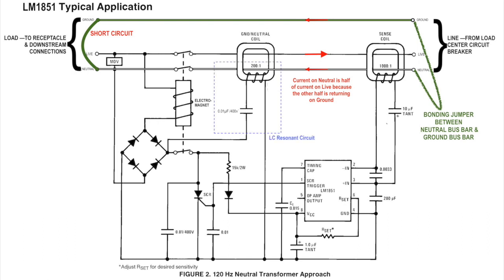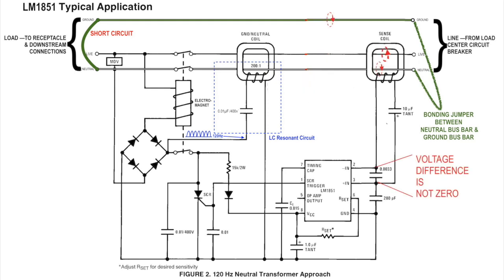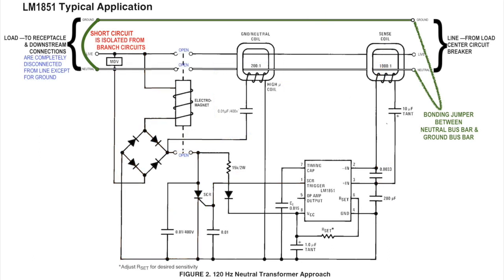To detect this, there is a second transformer which injects a high-frequency signal using the primary winding and a capacitor as a resonant circuit, excited by the 120 Hz ripple off the full-wave bridge. When the ground and neutral are shorted together, this signal is sensed by a difference by the sense coil and again trips the switches to deactivate the circuit and isolate the fault.